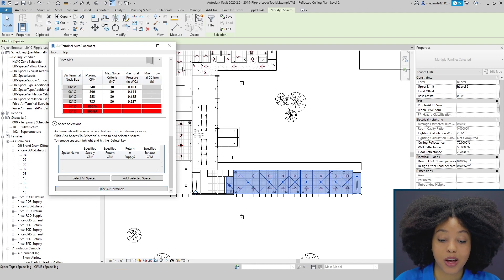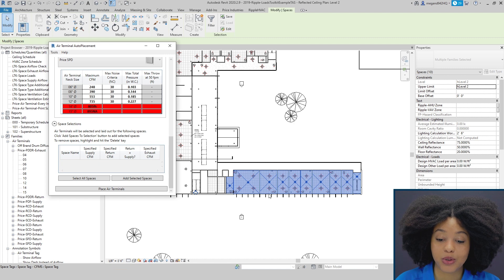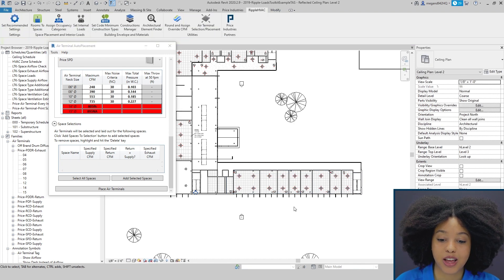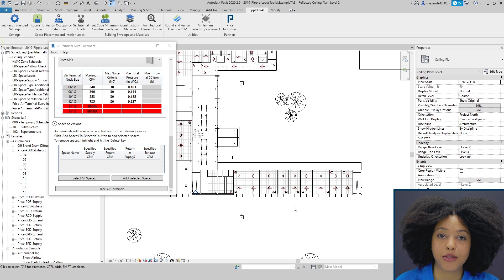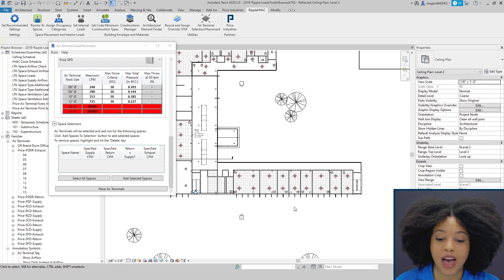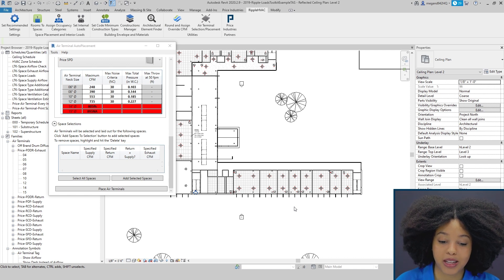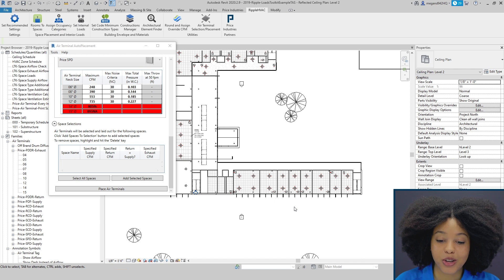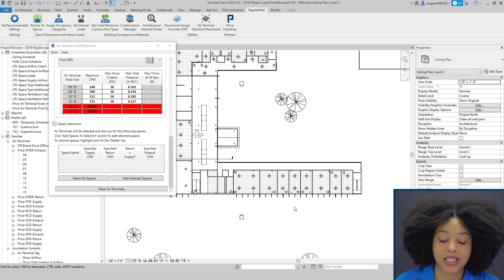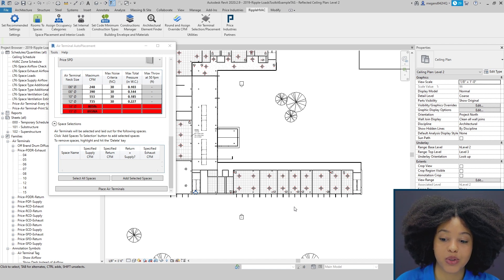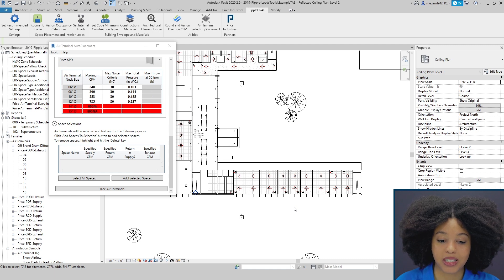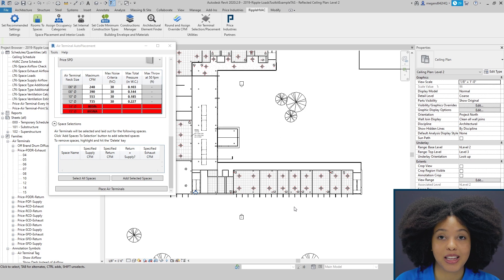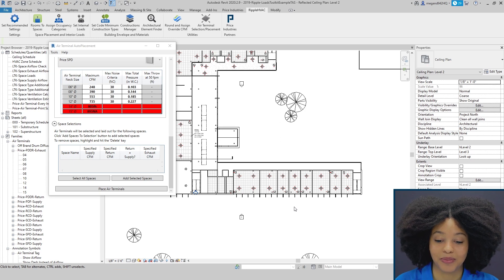The logic behind the tool is it takes a characteristic length and ensures that you have that 50 feet per minute throw at your occupied zone. It also divides your CFM according to the area within the project. It'll take a complex space and simplify it into a simpler space.